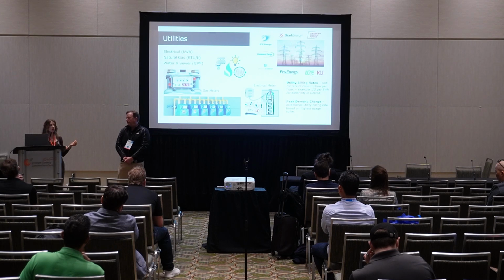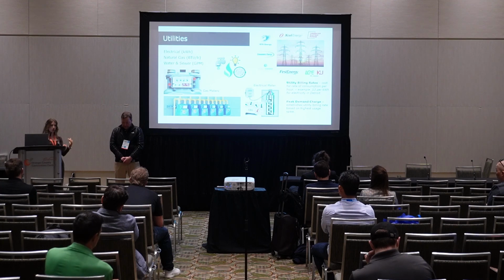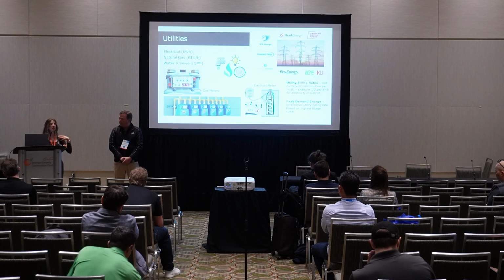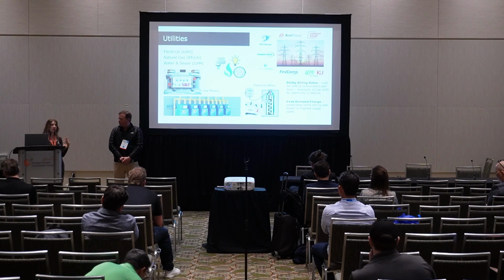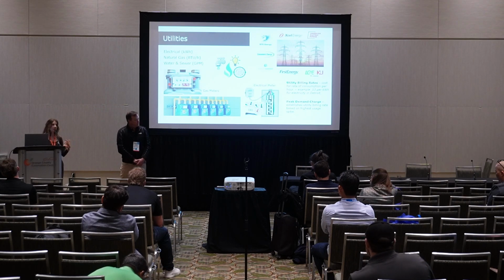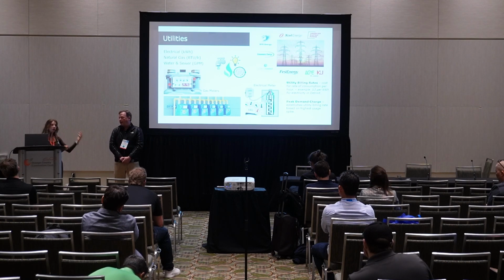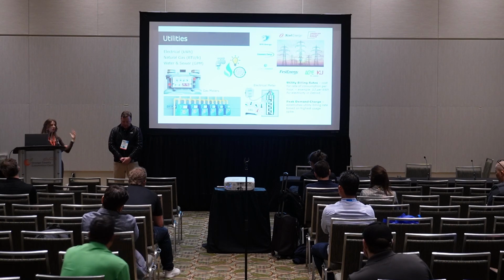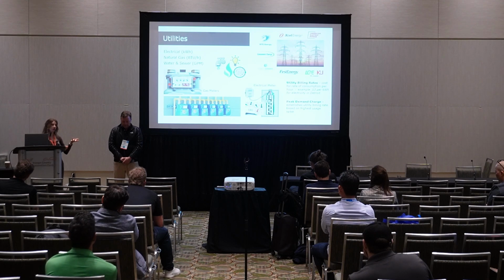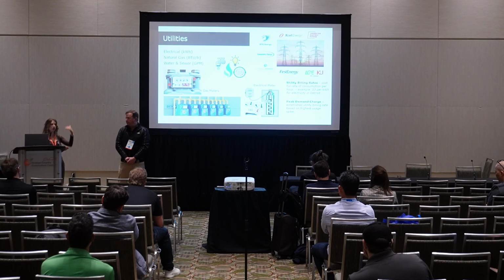The other way to do it is more like load management - not a response to a trigger, but pre-planning for it. An example would be a building with electric heat: typically my peak is probably going to happen first thing in the morning, when I'm warming up the building, everything's cold, and my electric boiler or electric heat pump is on. I know it's always going to happen then, so I don't need to set a threshold and drop it - I can just plan for that.